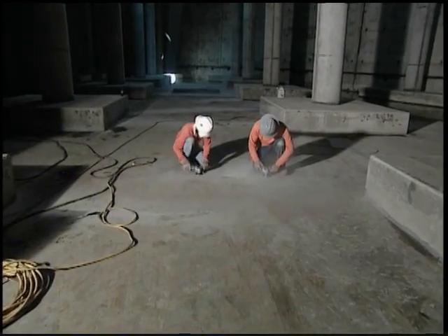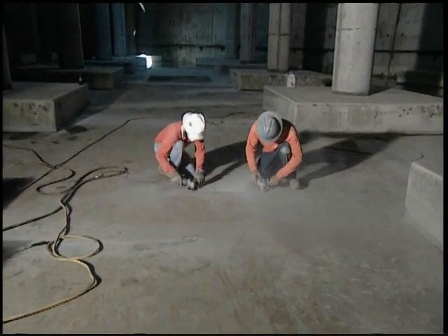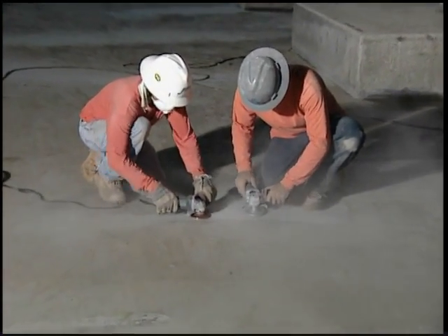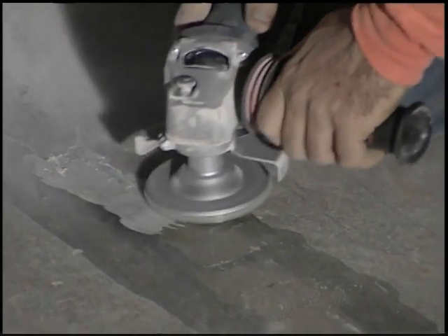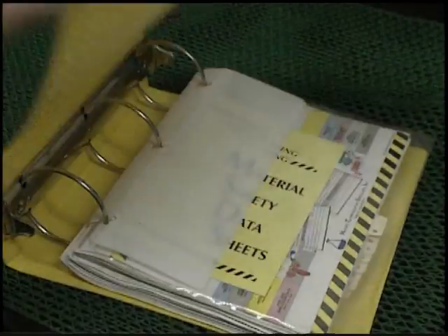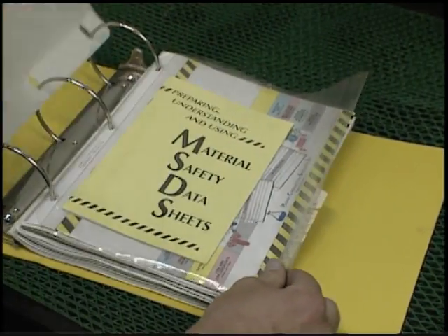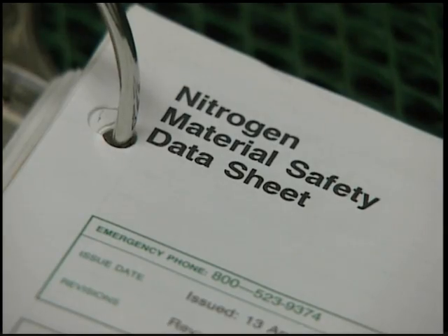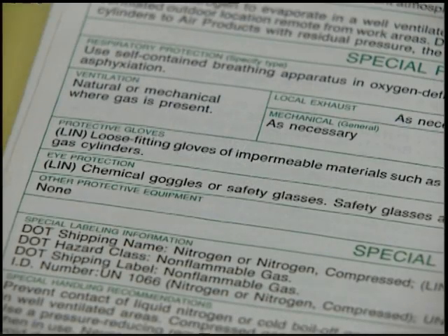The confined space atmospheric condition should also be evaluated to make sure there's not an airborne combustible dust concentration that obscures vision at a distance of 5 feet or less. And finally, it should be confirmed that the concentration of any substance is not equal to or greater than the allowed limit in the MSDS for that substance. The exposure information will be expressed as permissible exposure levels, or PELs.